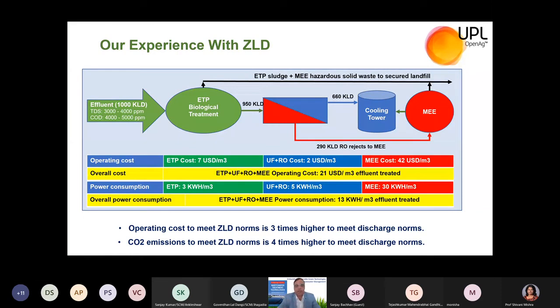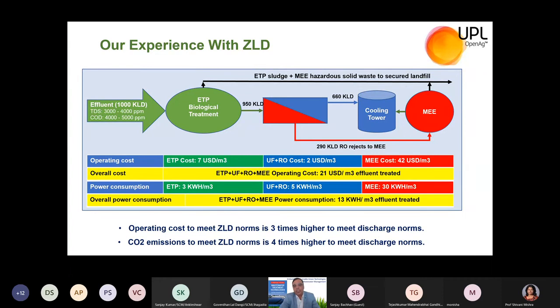If you adopt ZLD, the power consumption will be four times higher than a conventional system. Since energy is directly proportional to CO2 emission, we can say that CO2 emission to meet ZLD is four times higher compared to meeting standard discharge norms. The lesson from this slide is: don't adopt ZLD if it is not necessarily required.